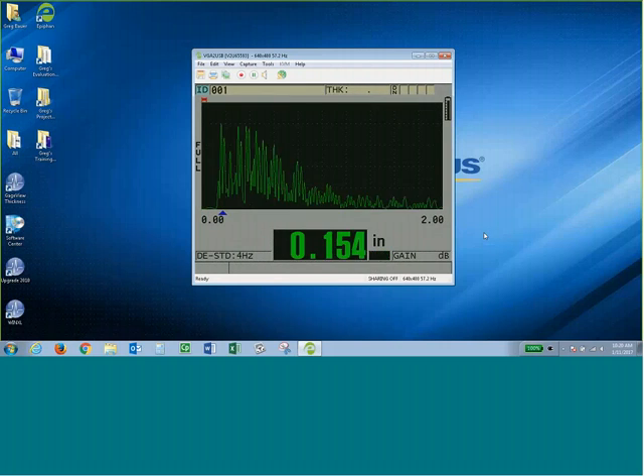Now you'll see on the 150, it reads correctly. When I go to the 300, I'm about 9 thousandths off. And 750, same thing, about 10 thousandths off. And 1.5, I'm reading correctly. So what I want to do now, because those steps in between really weren't within the accuracy that I want, or the specification for these transducers, is turn on that VPath builder.